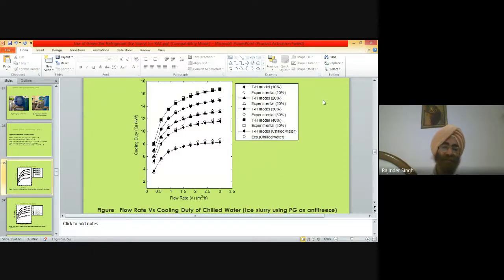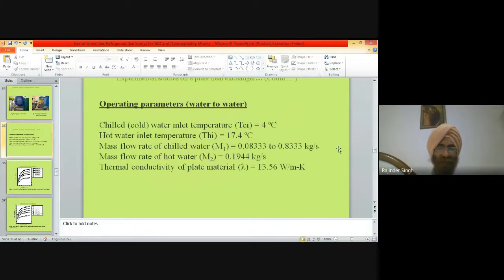Now this is the result. This graph shows the flow rate versus cooling duty, meaning the heat transfer, the cooling we achieved. This is the case of chilled water and ice slurry using PG as an antifreeze. In this diagram, this is the cooling duty, Q, and on the x-axis is the flow rate of chilled water and ice slurry. We varied the range in various steps, and that is how we obtained the graphs. Minimum is this and maximum is this.